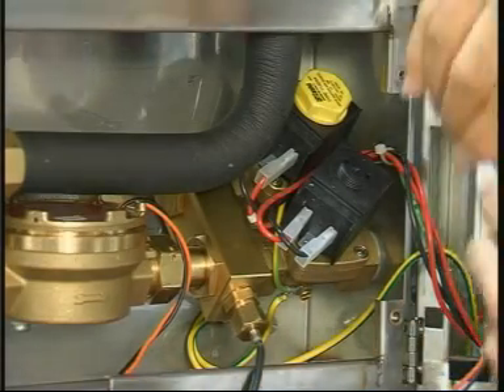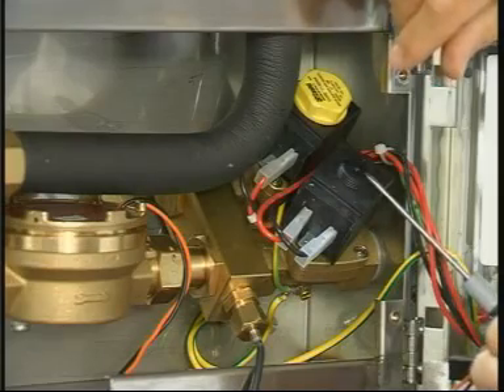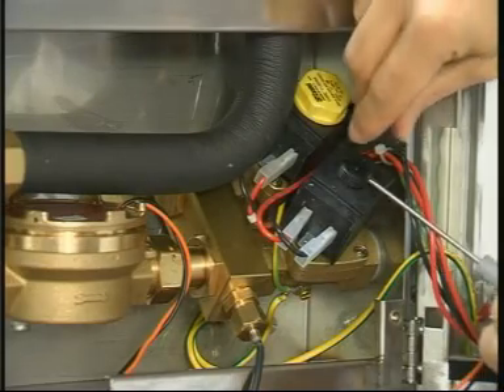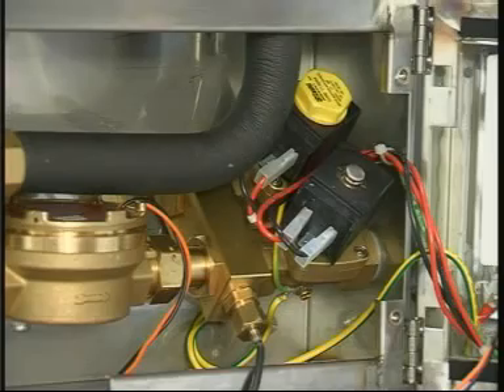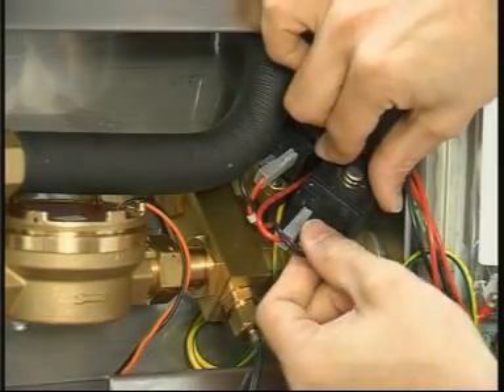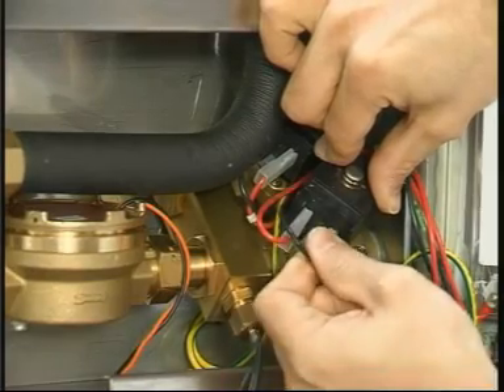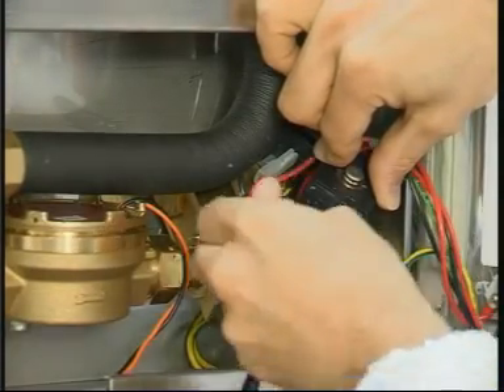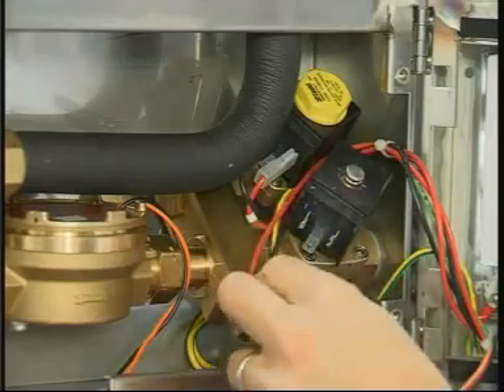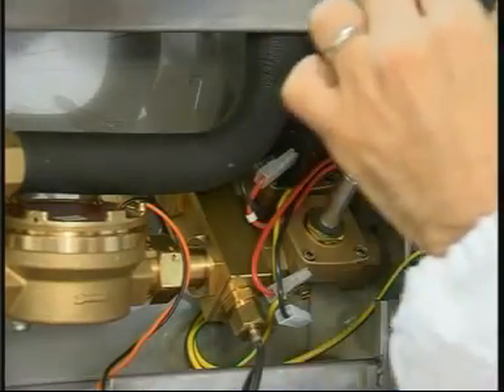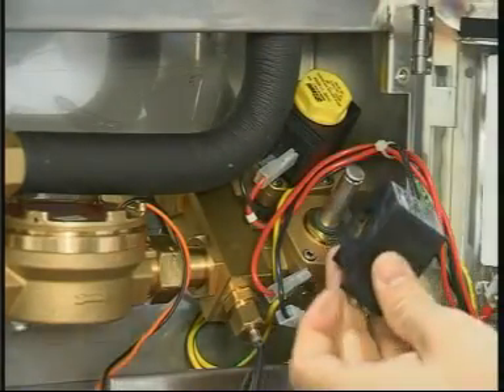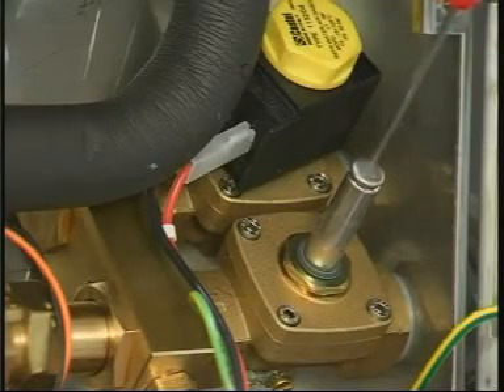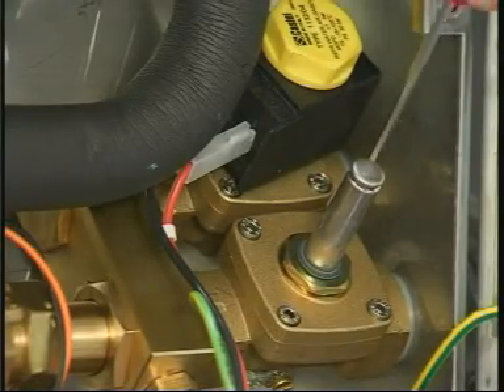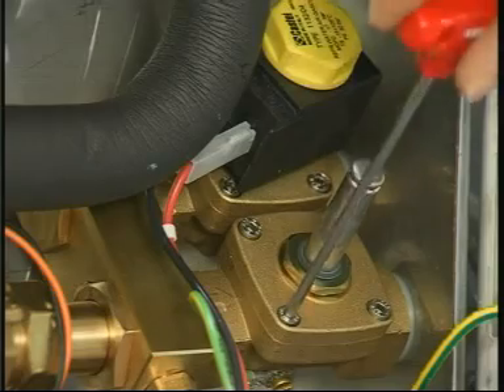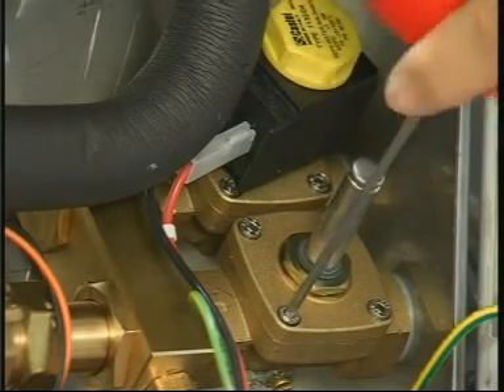Close the inlet ball gate valves and release the pressure. Switch off the supply to the machine. Unscrew the yellow stopper by hand. With a small screwdriver, remove the black plastic fastening rings. Disconnect the fastons and extract the coils. Unscrew the 4 socket head screws with an Allen wrench number 3.